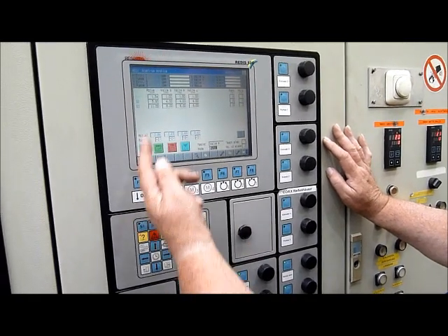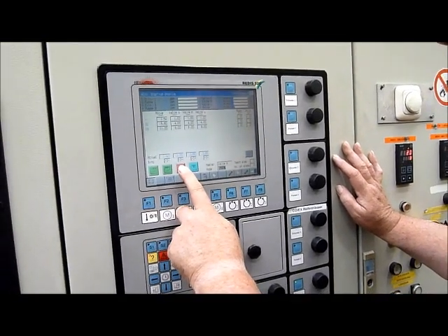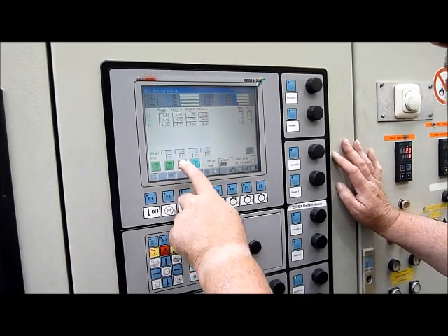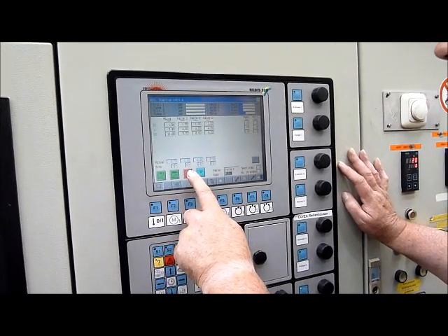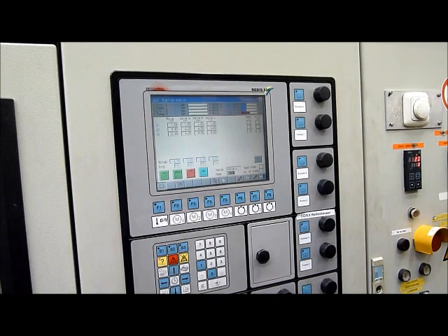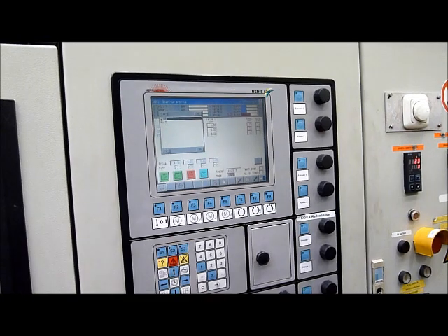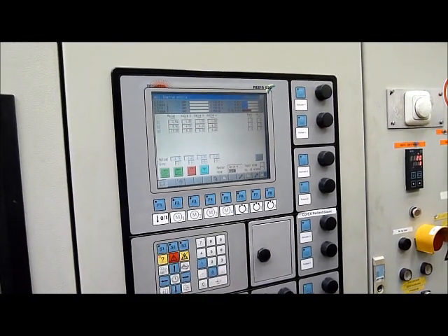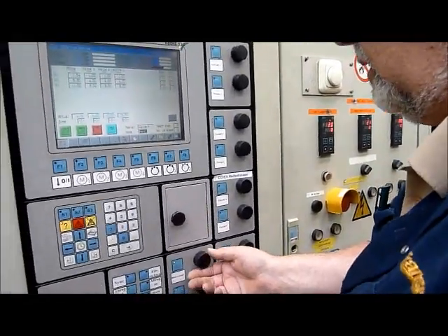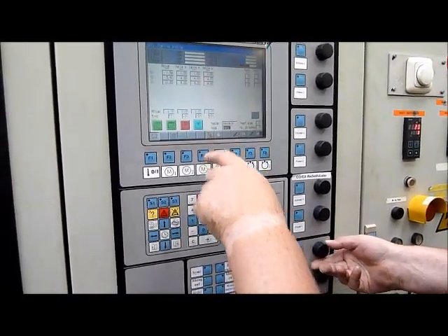The stop is actually stopping it going up or down, it's not stopping the rolls. So for instance, we want to run about, let's say 3 meters per minute. We'll let it ramp up to 3 meters on these roughly. Stop it there, that stopped the ramp. At this point, change back to hand. And now you can individually adjust the rolls and measure the peripheral speed of the rolls.